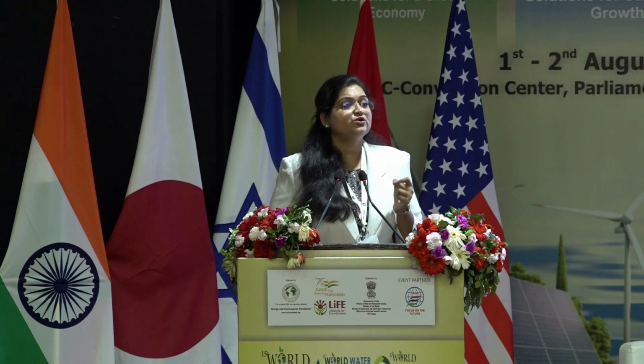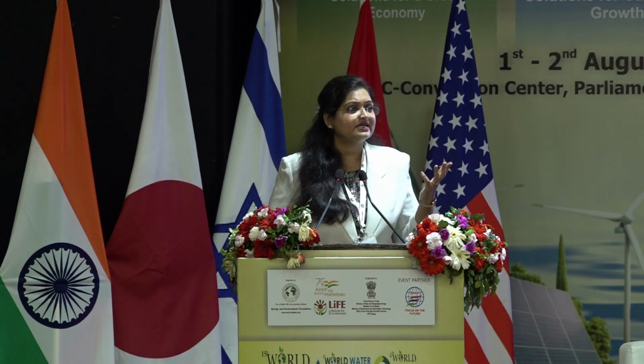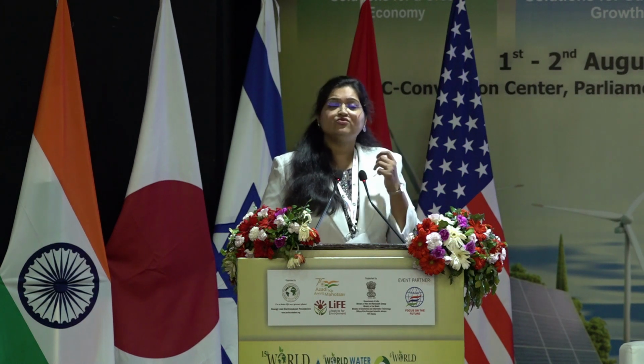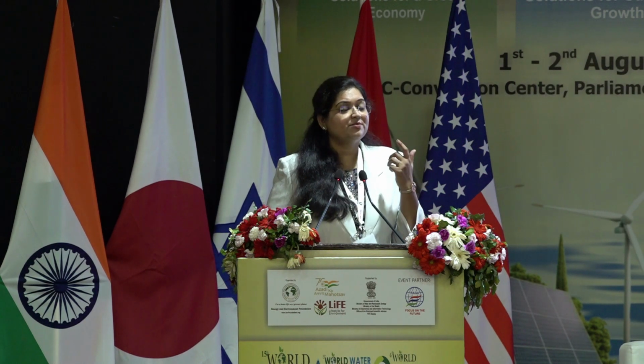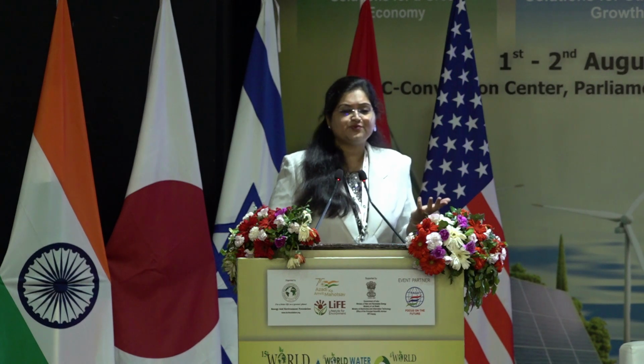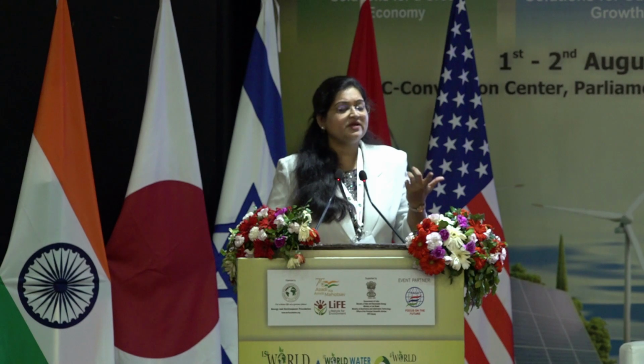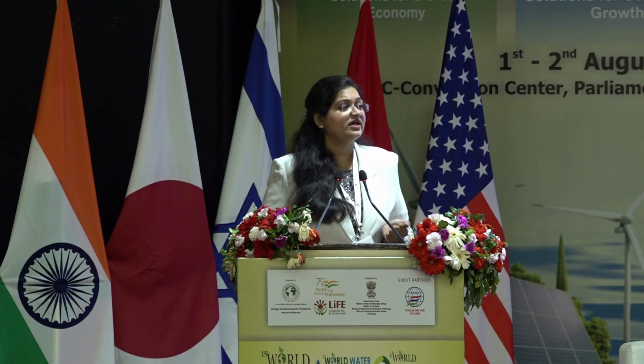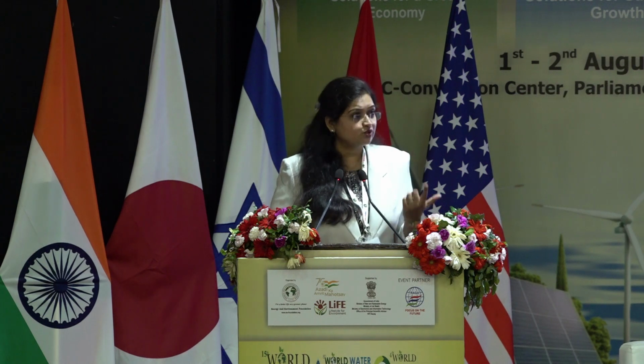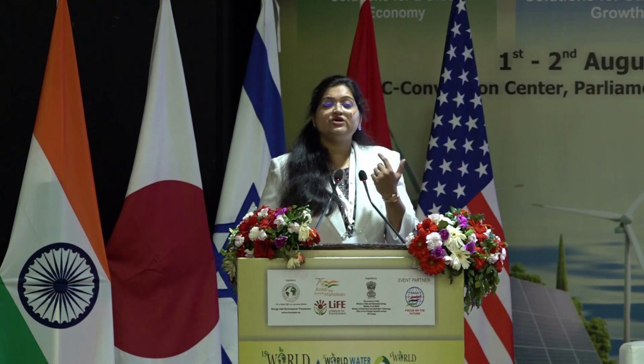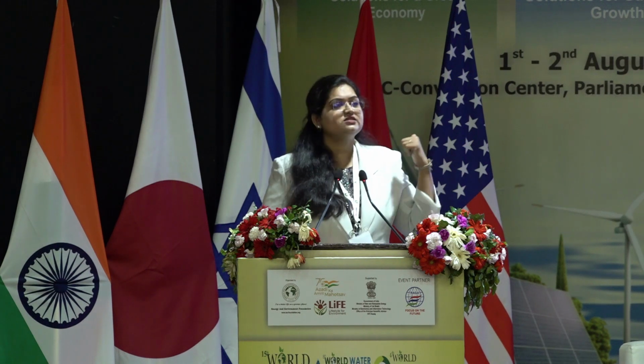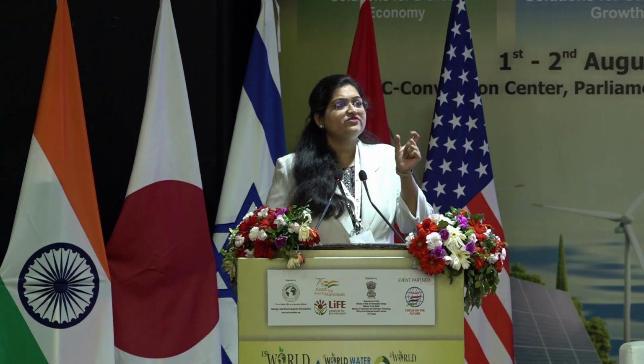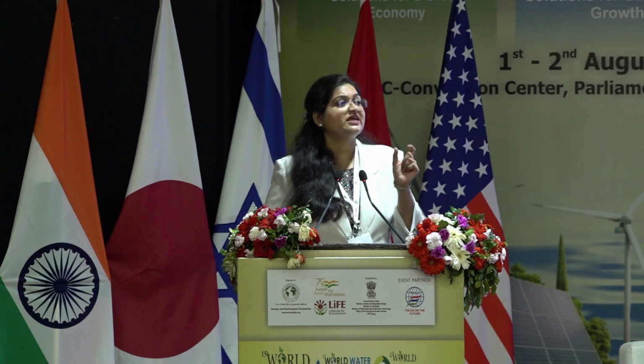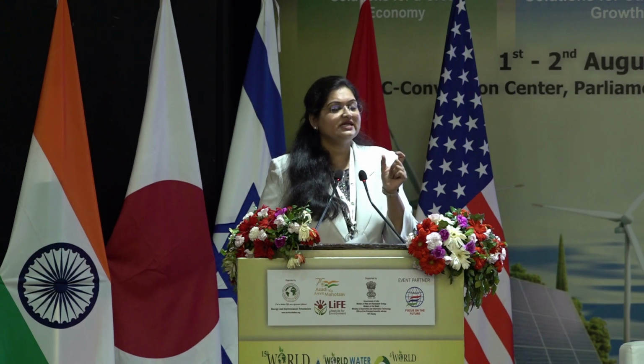Then there are important grid compliance studies. You'd like to see how it's helping the grid, how the harmonics look, what are the voltage and current bands, the power quality, the dynamic stability aspect, and so on. We can discuss this in detail some other time - you also have voltage ride-throughs defined for renewables. This typically specifies the amount of time for which a renewable plant should sustain a disturbance in the grid and stay connected, not causing any disruptions.